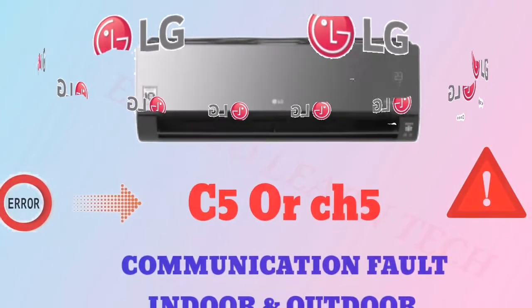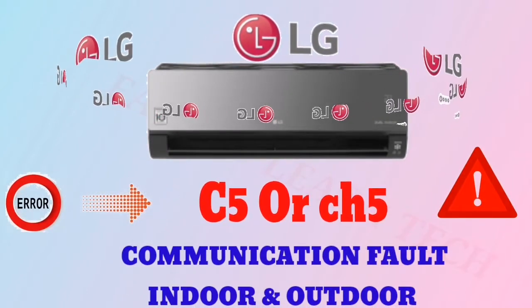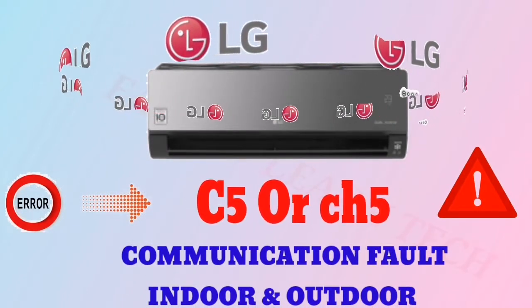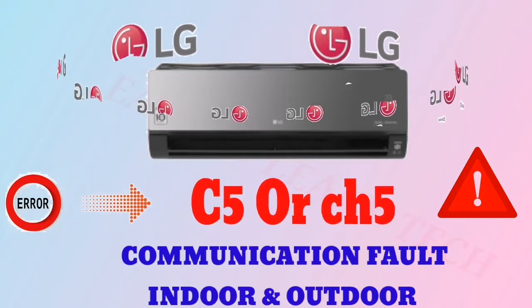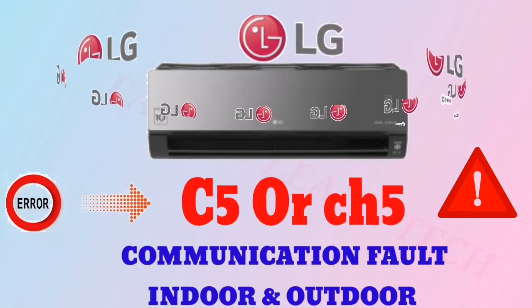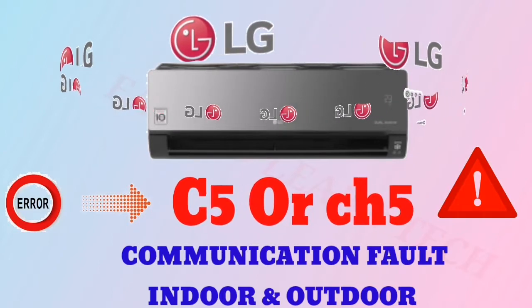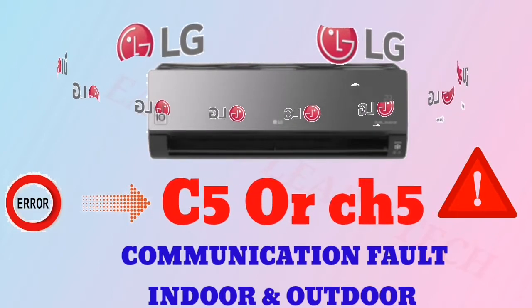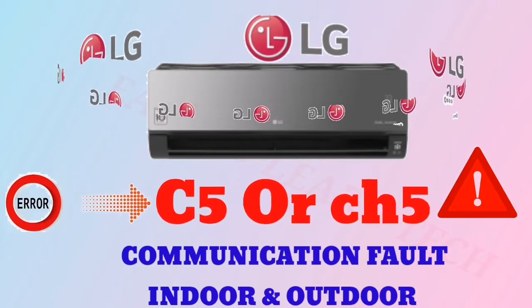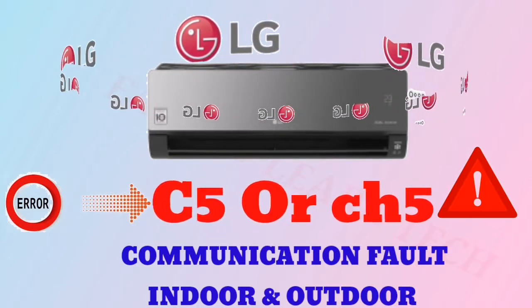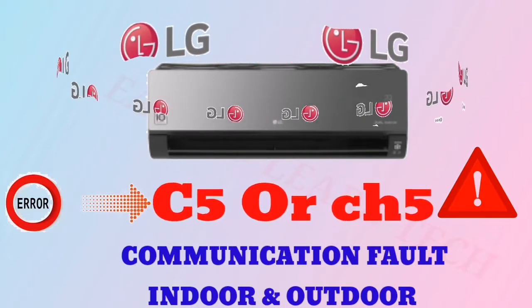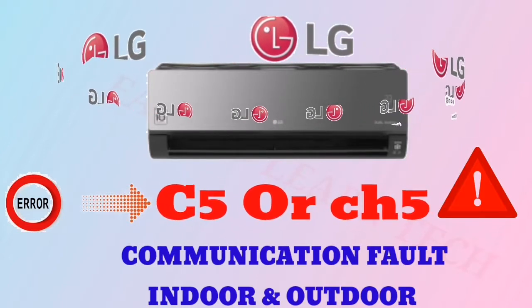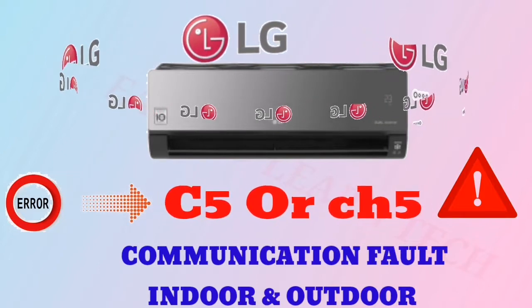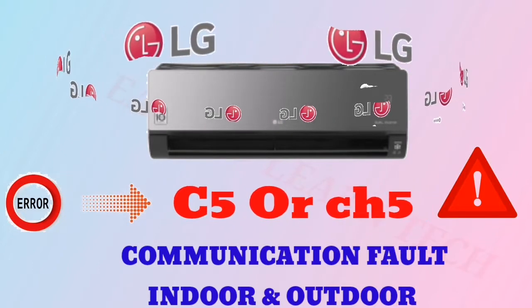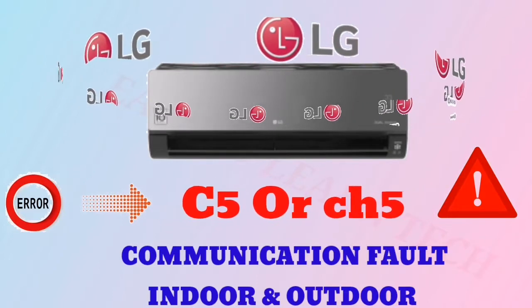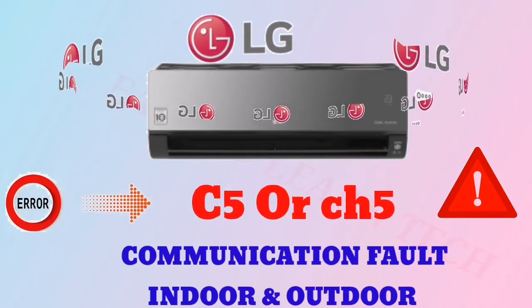Let's see the next error code and its solution. If you get C5 or CH5 on your display, it means communication fault between the indoor and outdoor unit. First of all, you have to check the cable between the indoor and outdoor. The communication cable should be perfectly connected in the indoor as well as in the outdoor. If it is perfectly connected, and again you are getting the same error, then you have to check the power output of our communication cable coming from our PCB. If it is between 13 to 24 volts, it means our indoor PCB is okay. If the voltage is not coming from the indoor PCB, it means the indoor PCB is faulty and you need to change it. And if the power is coming and again you are getting the same error, then you have to change the outdoor PCB and your unit will be in working condition.